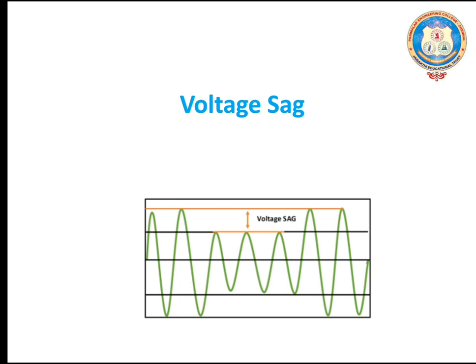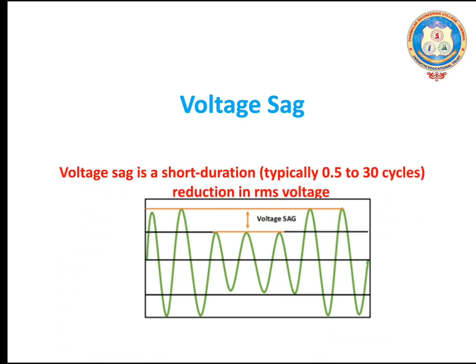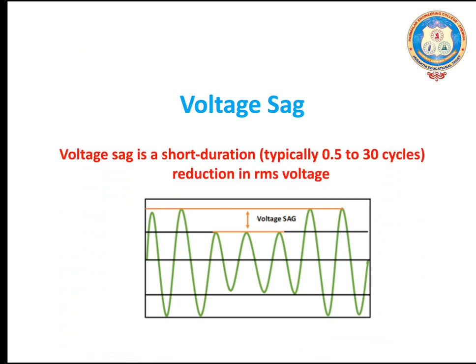What is Voltage Sag? Voltage Sag is a short duration variation in which there is a reduction in RMS voltage, which occurs typically by 0.5 to 30 cycles.